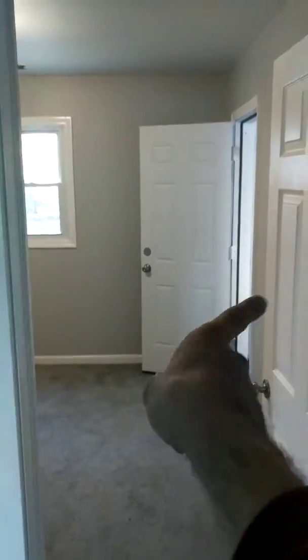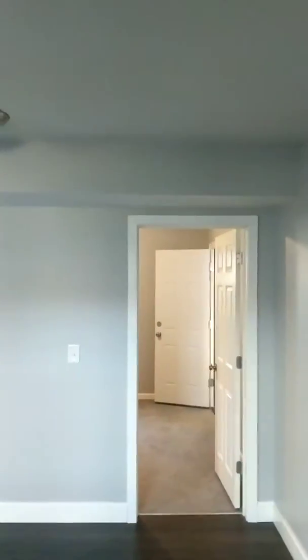For your smokes, sir, in this bedroom, which is right outside the garage, make sure you get a smoke alarm there. You're also going to need to have a carbon monoxide and a smoke alarm on the ceiling within 8 feet of the door. So just put one here, whether you put a combo or you put two. Just make sure there's a smoke and a carbon.